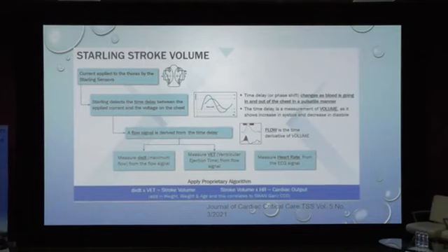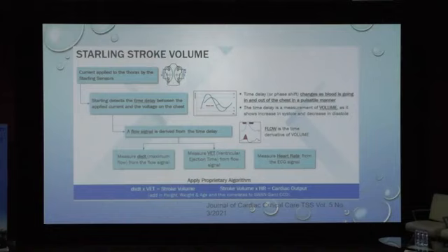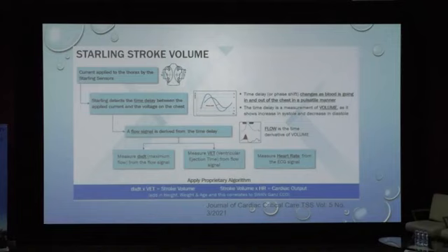The Starling Bio machine from Baxter works on this principle. Two pairs of electrodes — inner and outer — are pasted over the chest, creating a current field. The machine detects the time delay between the applied current and the voltage in the chest. This time delay or phase shift changes as blood flows in and out in a pulsatile manner and is measured as a unit of volume. A flow signal is derived from this time delay, giving maximum flow, ventricular ejection time, and heart rate from the ECG. The formula applied is dx/dt × VET = stroke volume, and stroke volume × heart rate = cardiac output.